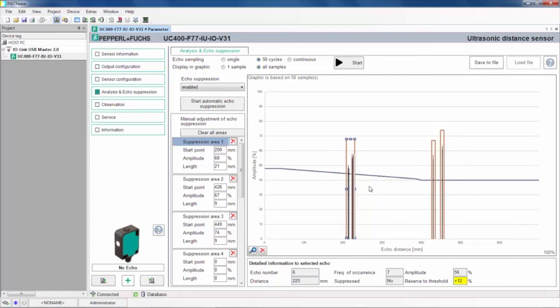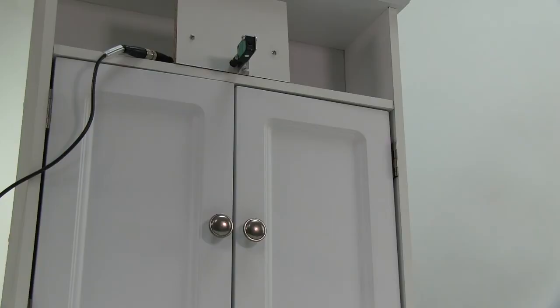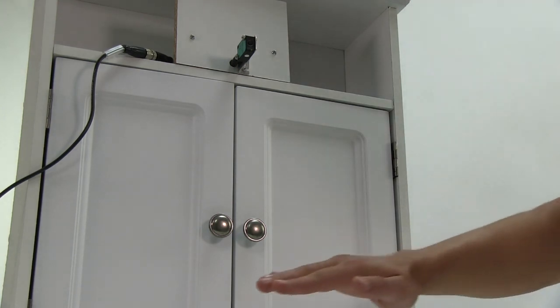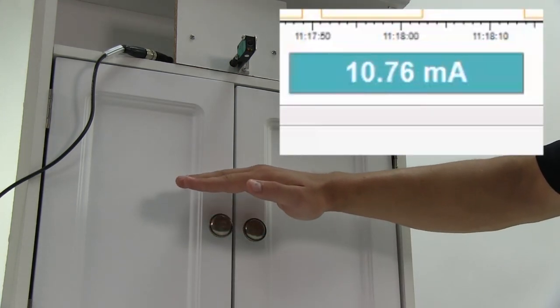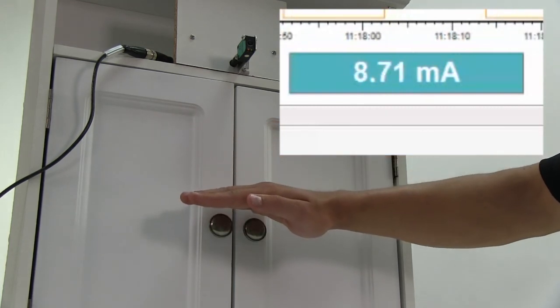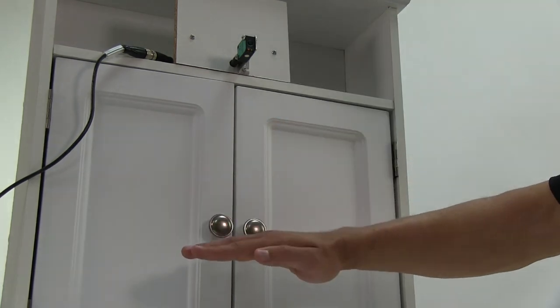Let's go back to the sensor and cabinet setup to see how the sensor functions now. With those unwanted reflections eliminated, we can now get a continuous output from below the handles all the way up to the dead band of the sensor. This capability opens up a wide variety of new applications where an immovable object would have previously prohibited the use of an ultrasonic sensor.